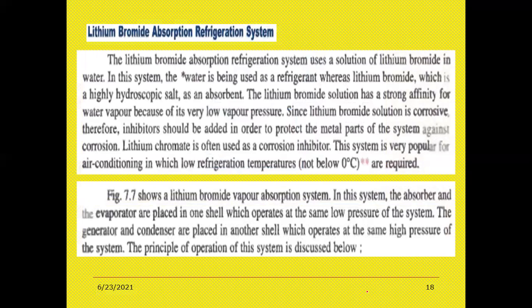Now we'll discuss the other type of refrigeration system in the absorption system, that is the lithium bromide absorption refrigeration system. So what is the other one? Lithium bromide absorption refrigeration system. Now we'll see the next category. The lithium bromide absorption refrigeration system uses a solution of lithium bromide in water. Here in this system, the water is being used as a refrigerant.